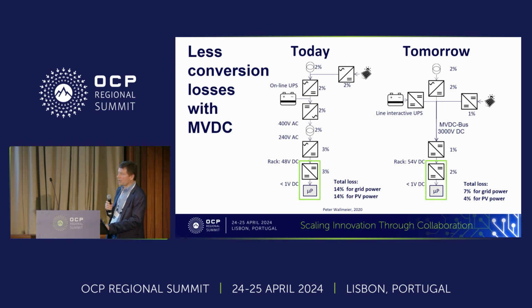Here we have the grid, we have the active front end. The UPS is now line interactive. The PV converter has a better conversion efficiency because we do not have to have the hassles with AC. There's the MVDC bus, 3 kilovolts. There is one converter which is producing the 400 volts. It's the power box, and then it goes into the rack, and there is the power shelf powering the servers. So when we sum up all the losses, now for PV energy, for example, we are at 4% instead of 14%.